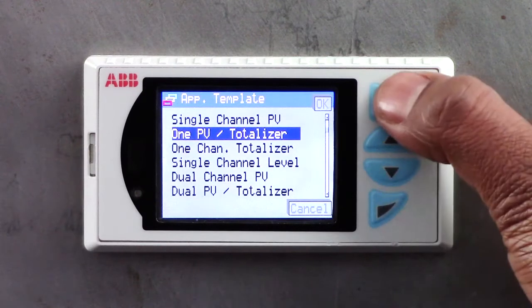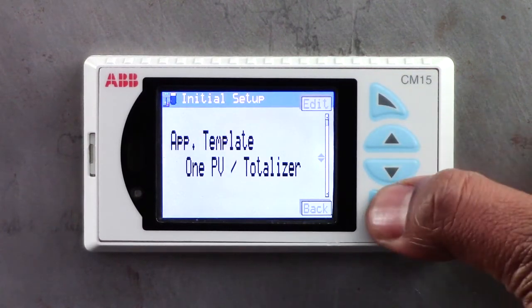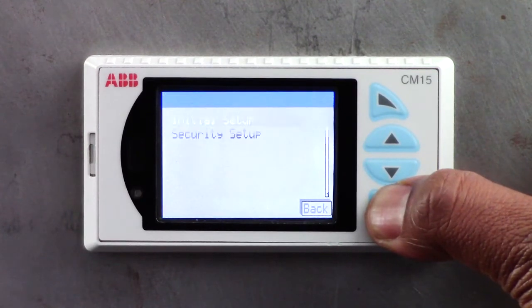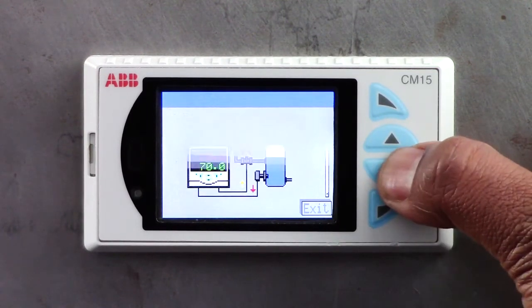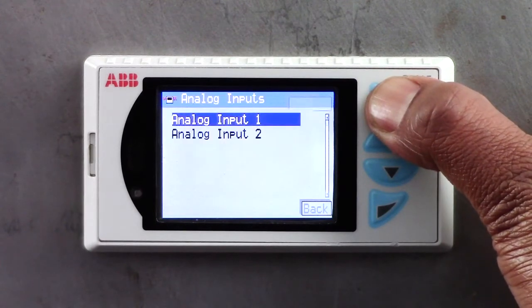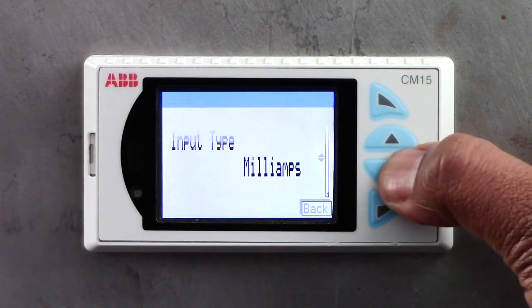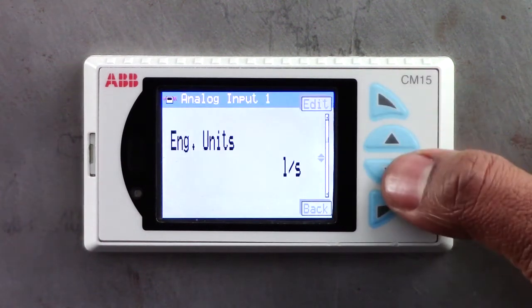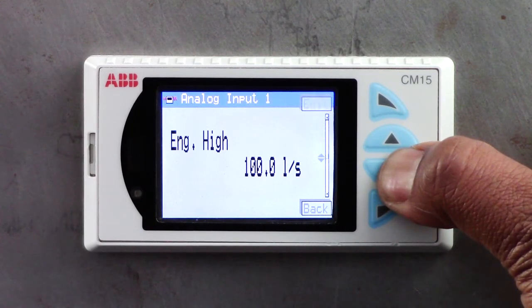In this video I have selected the 1PV totalizer template. Once you have selected the required template, go into the input output menu option and select the appropriate input type. In this case it's a 4-20mA signal representing a 0-100 litres per second instantaneous flow rate.